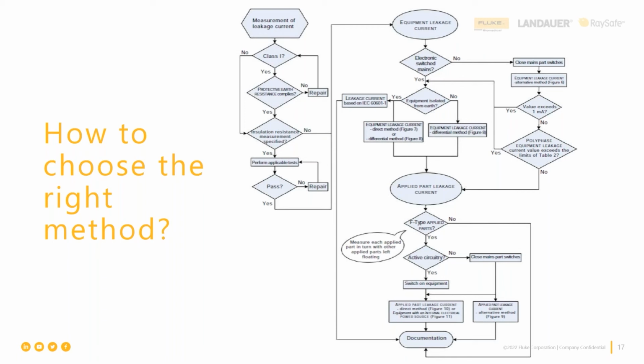And this decision tree, or flow chart, if you will, helps us make the decision about which of the 3 testing methodologies is the right one to use for the particular brand and model of medical device or category of medical device. So there are 3. They are direct, differential, and alternative. And the one that is most like the IEC 60601-1 is the direct method.